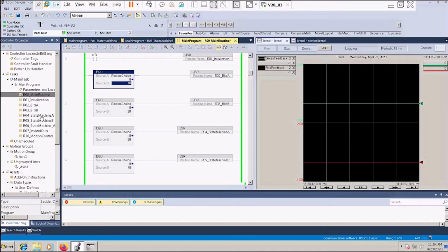Whereas if you were using state logic specifically to the motion stuff, right? I mean, there are times when you have to interlock bits and things, but when you do motion, you can actually see machines not quite work the same way with just a faster processor, even keeping all of the logic in the same sequence. Right, and that's where a state machine would help with that. Even though it's in the same sequence, the state machine can keep you in that state longer, perhaps, or until the reaction happens instead of perhaps blowing through. Granted, you can make mistakes with a state machine. I can screw things up many ways as well, but still, the point being, ease of documentation, ease of troubleshooting for others, other than yourself if you're the original programmer. And again, it's very conducive to motion.